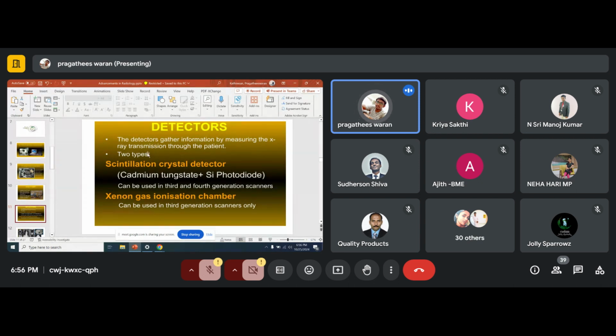While converting X-ray to light energy and then from light energy to electrical energy, some wastage will be there, and some dead points, so some of the images will be blurred because of these dead points. So nowadays direct crystal semiconductors are being used. The crystal semiconductors directly convert the X-ray into an electrical signal, which we can measure and process, and we get very good image clarity. These are some of the advancements in detectors.